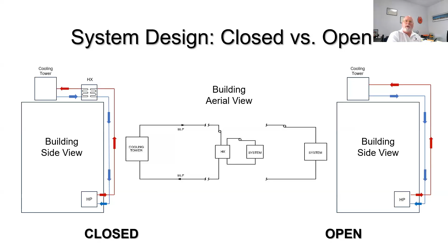Unfortunately, a lot of times we can't change from open to closed because of structural limitations, but this is what the feasibility study helps us determine. For example, those heat exchangers alone can weigh thousands upon thousands of pounds, which a roof may or may not be able to support. We also need additional pumps for a closed system versus an open one, and sometimes the electrical system just can't support it. So while it'd be ideal to switch from open to closed for maintenance and efficiency reasons, sometimes it's not possible — but it's always worth at least a quick look.